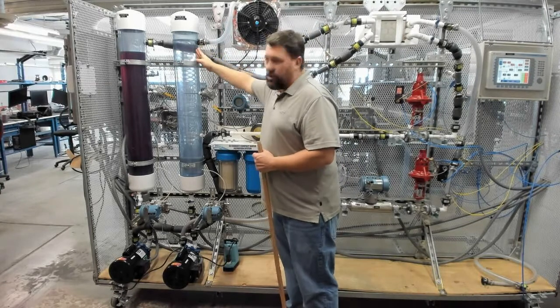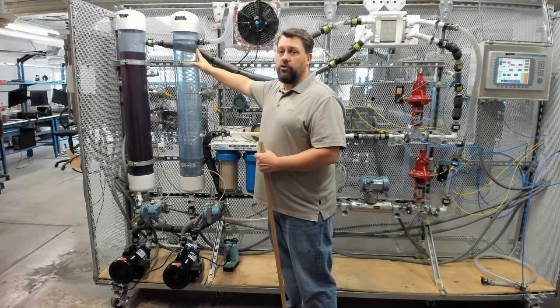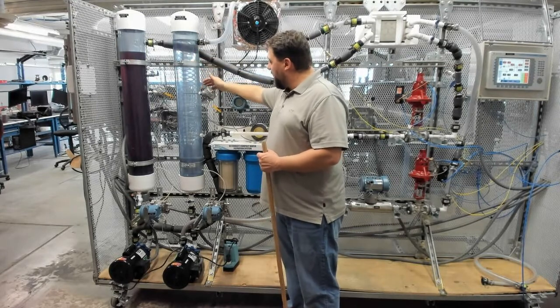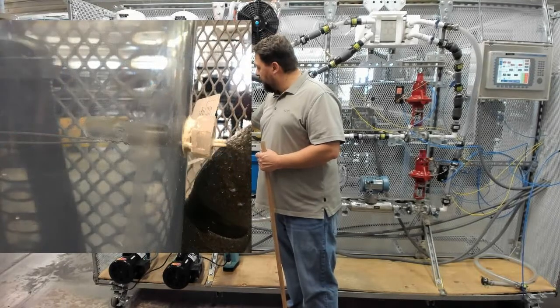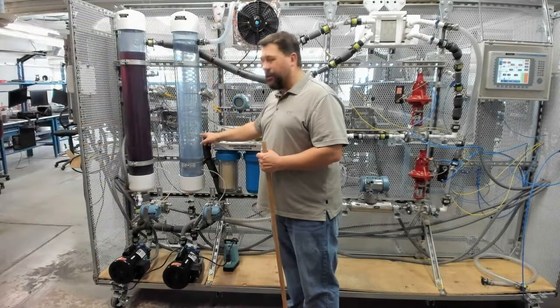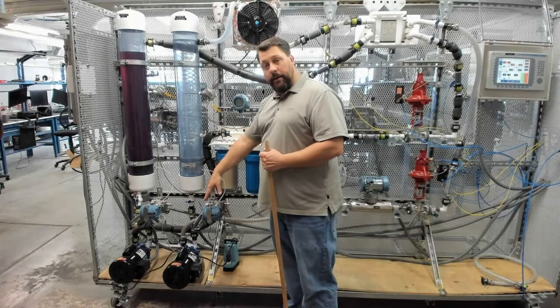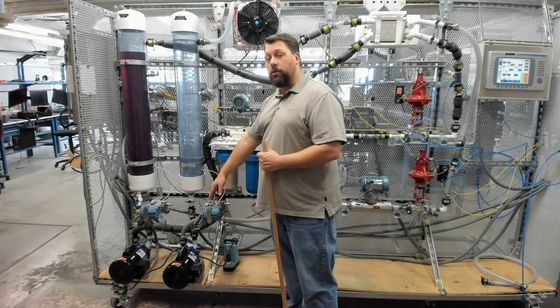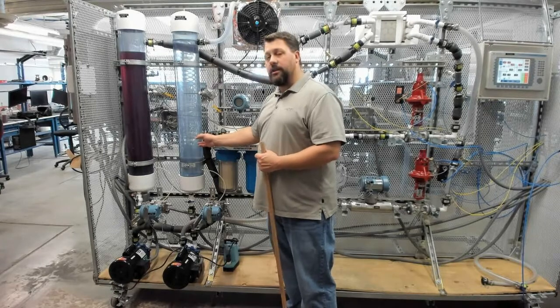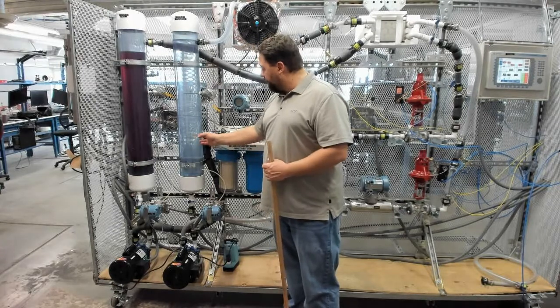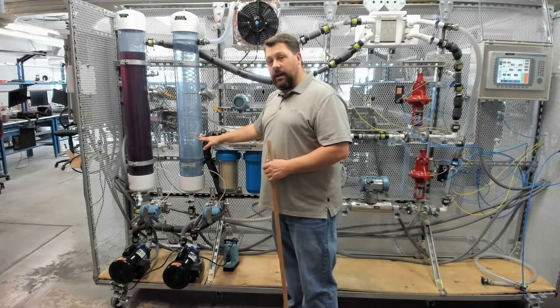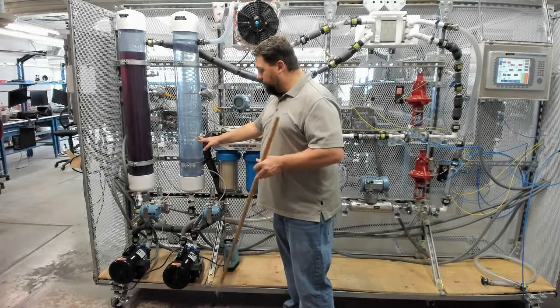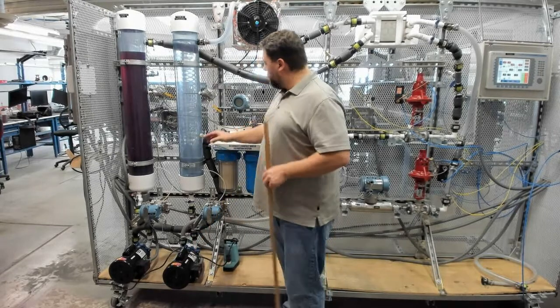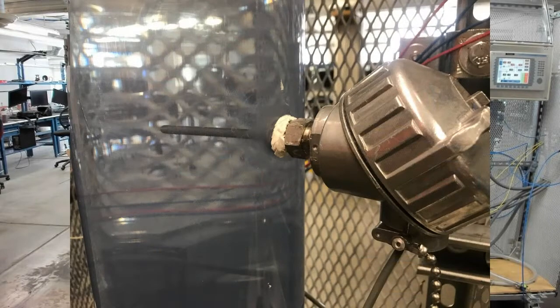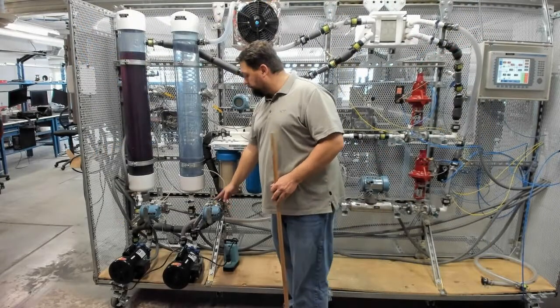Again, in this tank, there's no heating element, so we don't really need as many motor control things. All we really have here is one float switch, or a level switch, right here. Essentially if the water drops below this point, then the pump would not work. So that's a motor control safety function. You'll see that in your ladder diagram, where if this float switch is not in a true position or closed, then you would not be able to run the motor. Again, we have instrumentation here, temperature and pressure based level measurement.